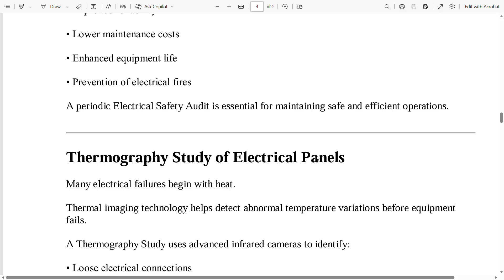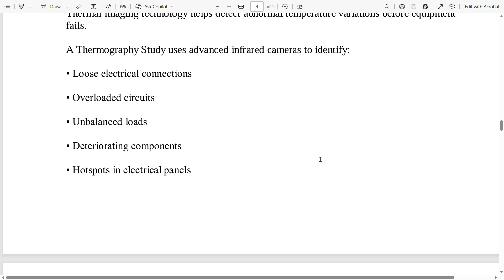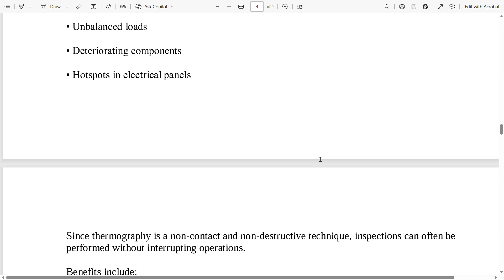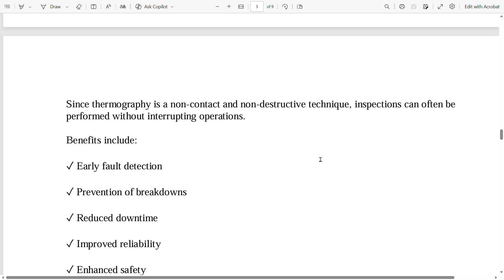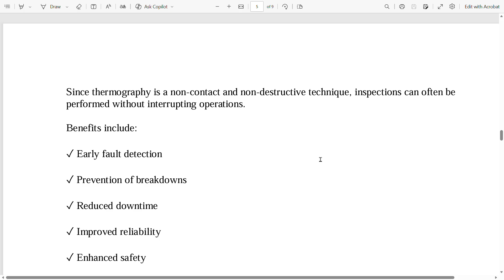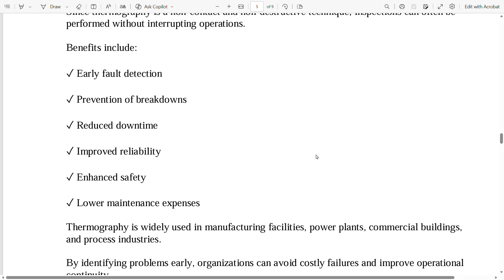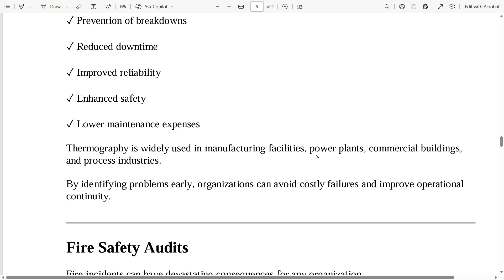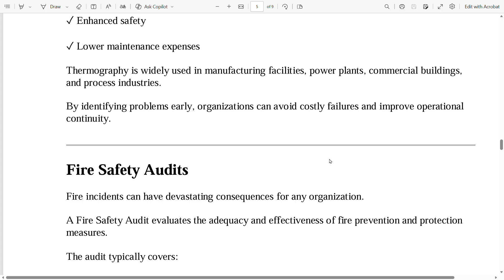Thermographic study of electrical panels. Many electrical failures begin with heat. Thermal imaging technology helps detect abnormal temperature variations before equipment fails. A thermography study uses advanced infrared cameras to identify loose electrical connections, overloaded circuits, unbalanced loads, deteriorating components, and hot spots in electrical panels. Since thermography is a non-contact and non-destructive technique, inspections can often be performed without interrupting operations. Benefits include early fault detection, prevention of breakdowns, reduced downtime, improved reliability, enhanced safety, and lower maintenance expenses. Thermography is widely used in manufacturing facilities, power plants, commercial buildings, and process industries. By identifying problems early, organizations can avoid costly failures and improve operational continuity.